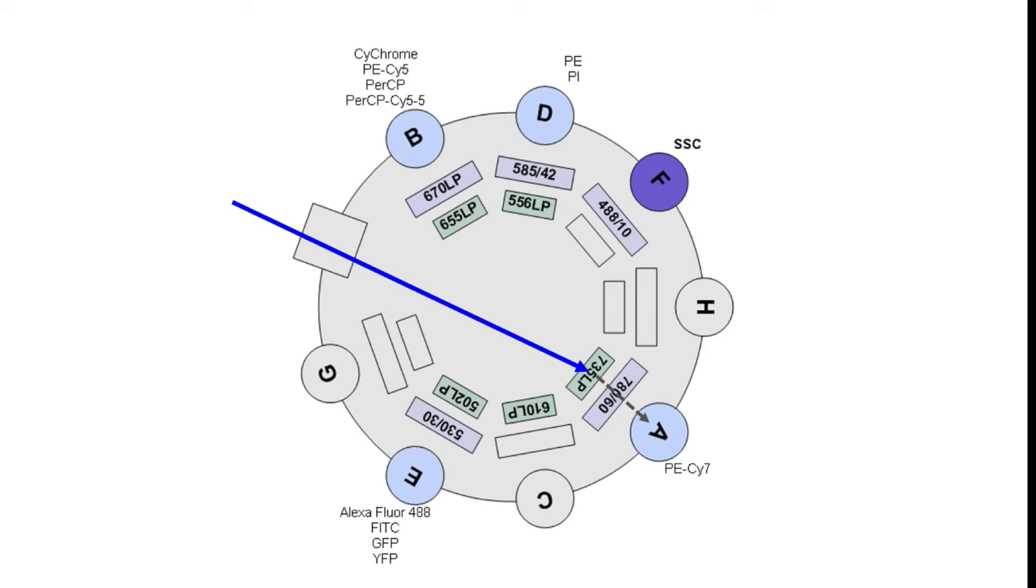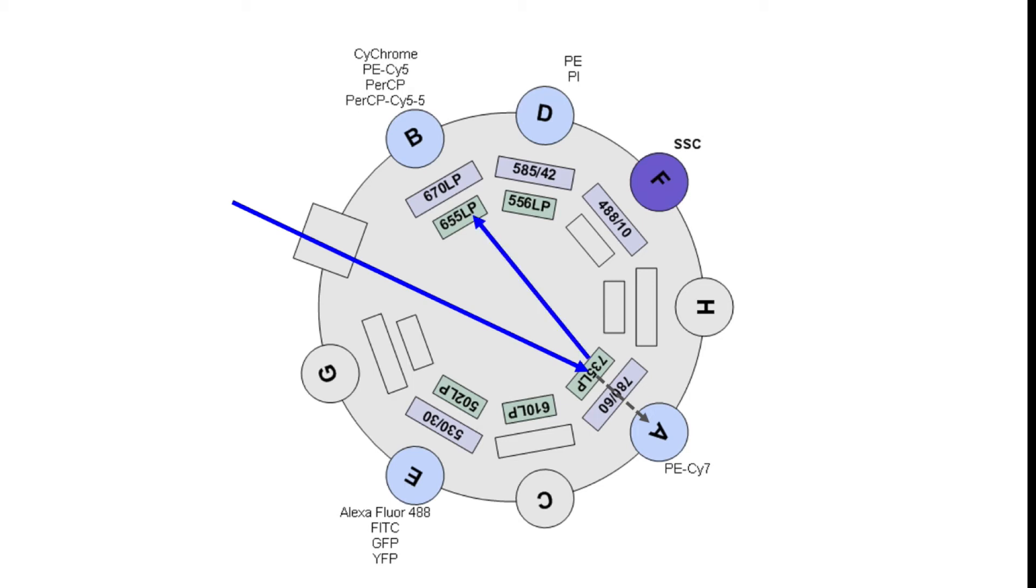If we go back to the 735 long pass, this filter is set up as a dichroic mirror so any of the light that did not go through and was shorter than 735 nanometers will bounce and hit the next long pass filter which is a 655 long pass, and the light will continue to bounce around this filter set until it finds a filter that it can pass through.